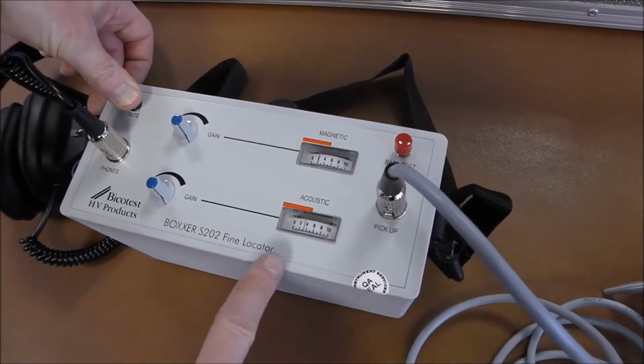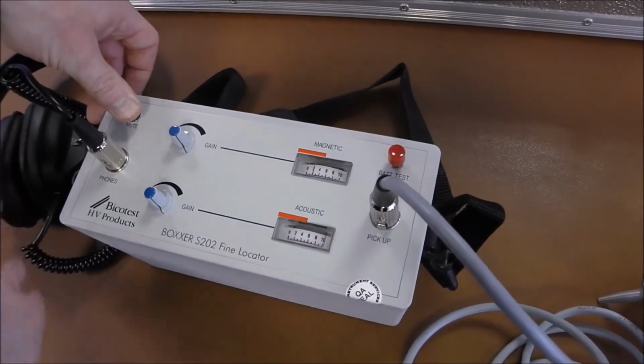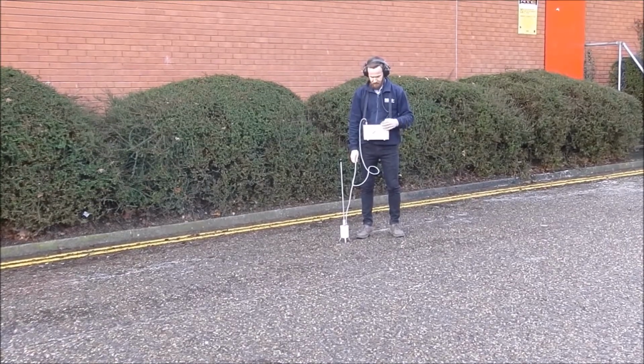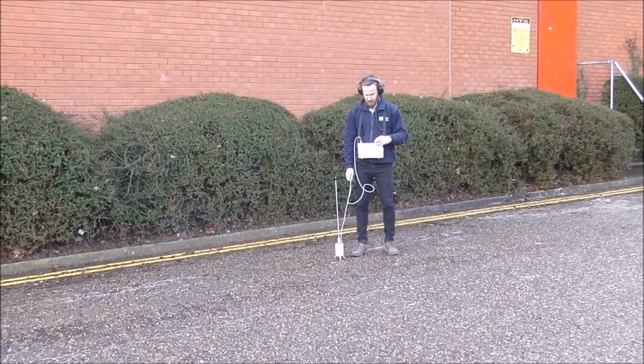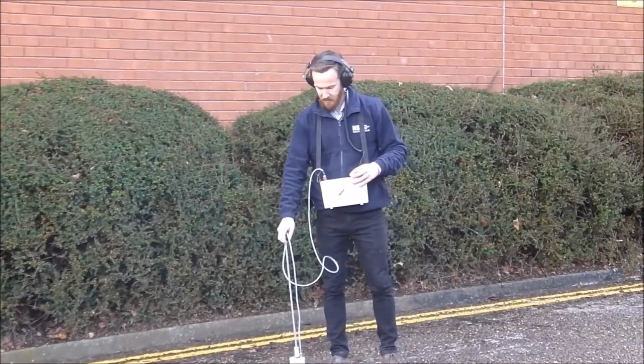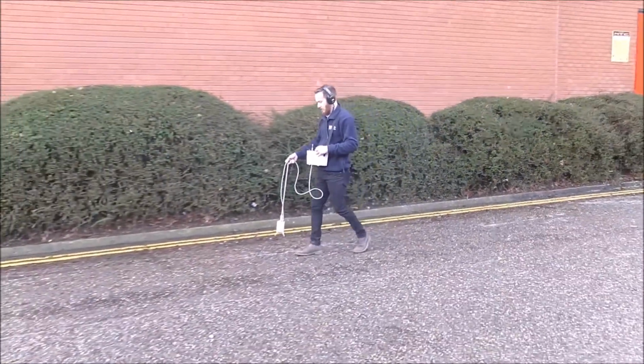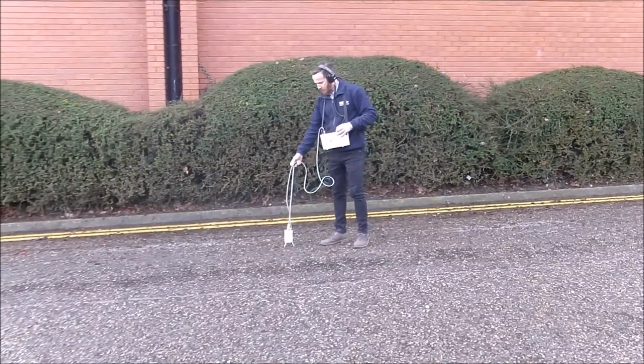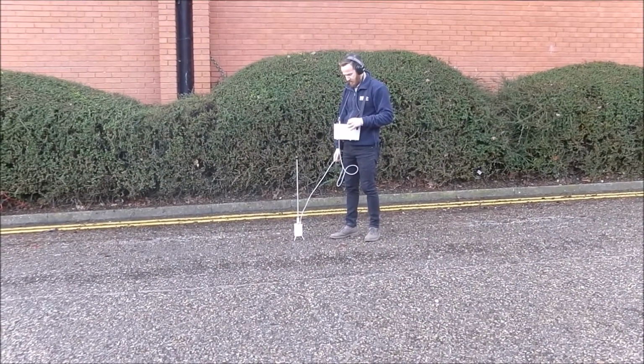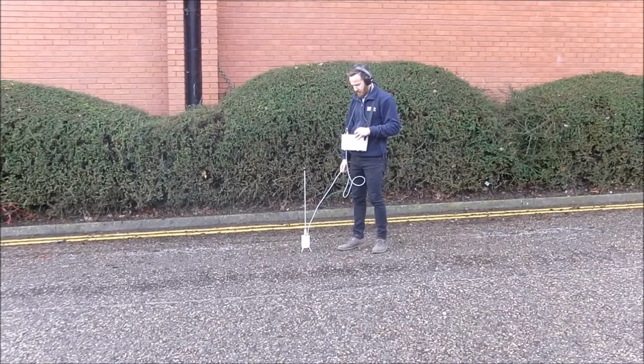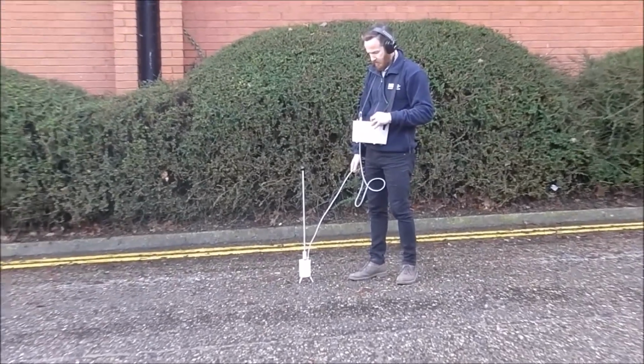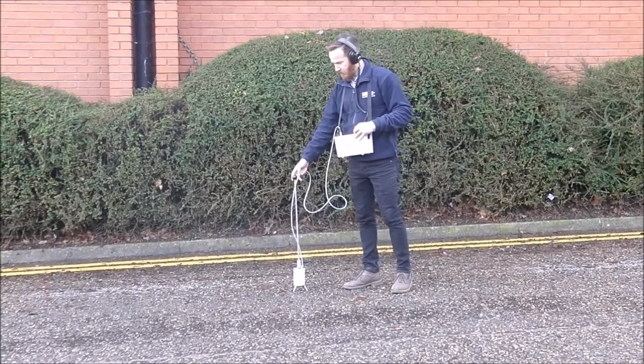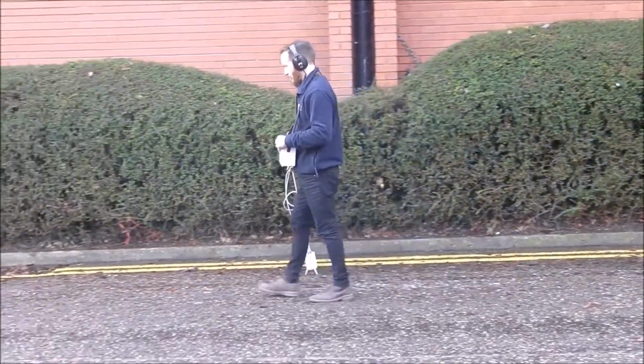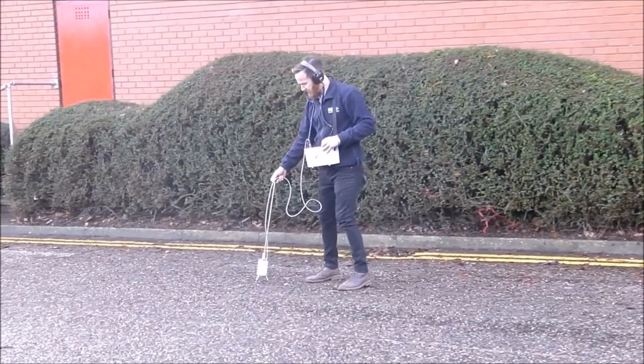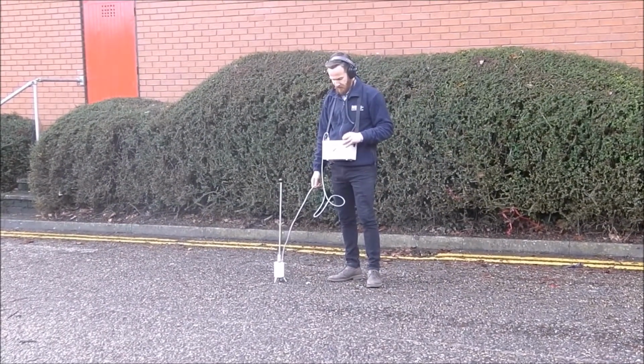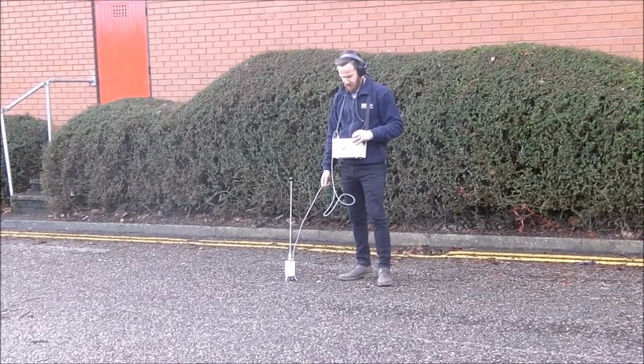With the exception of short lengths of cable, it is normal practice to carry out a preliminary fault location from the cable terminations by one of the standard pre-location methods to determine the approximate position of the fault and thus the search area. This area is then investigated with the S202 fine locator and the precise position of the fault is pinpointed. Set your surge generator to discharge into the fault conductor at regular intervals, say 3 to 5 seconds. The voltage and capacitance selected will depend on the rated voltage of the cable and the fault characteristics, but for best results, the highest values practicable should be used.